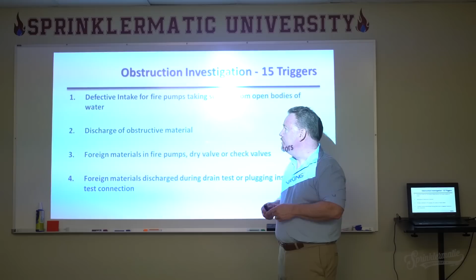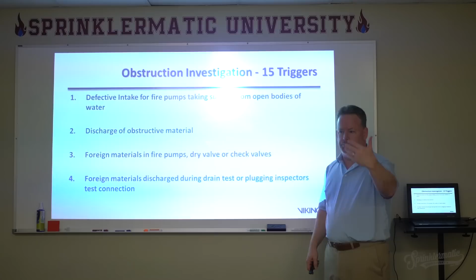So basically what we're doing there. Now before we get into the obstruction investigation, basically what we're looking for during an interior inspection of pipe is this: you pull the system apart, you take a couple of sprinklers off. Mostly now, what we're doing with this is either cameras, draining the system and then running cameras up into the piping, using non-destructive methods, because we're not taking sprinklers off. So you can do X-rays or internal cameras and things like that to do your internal inspection assessment.